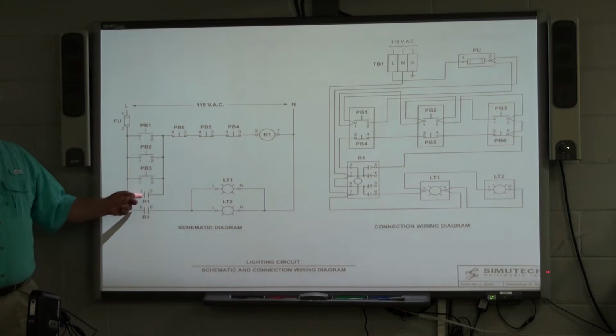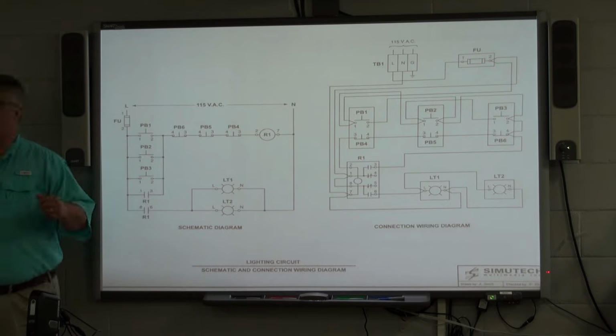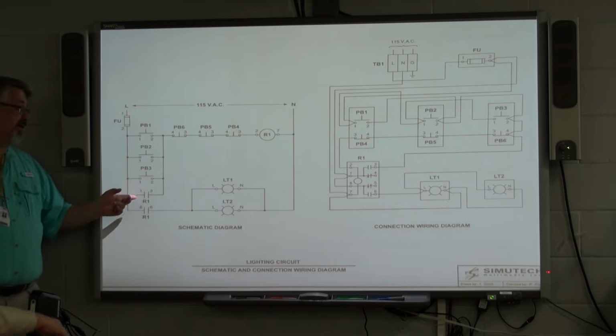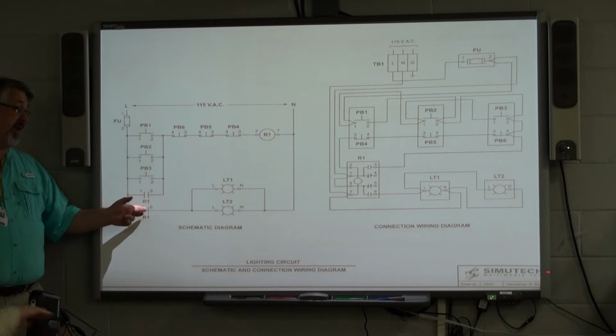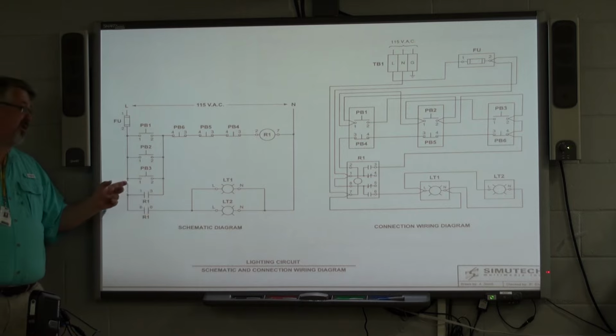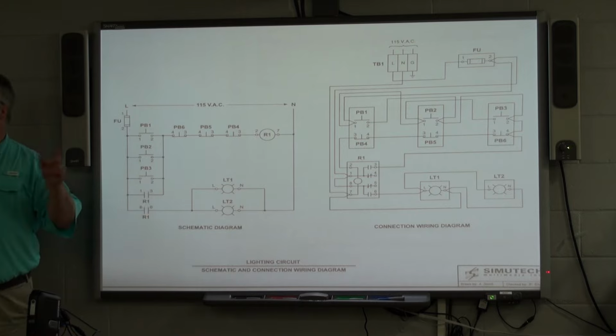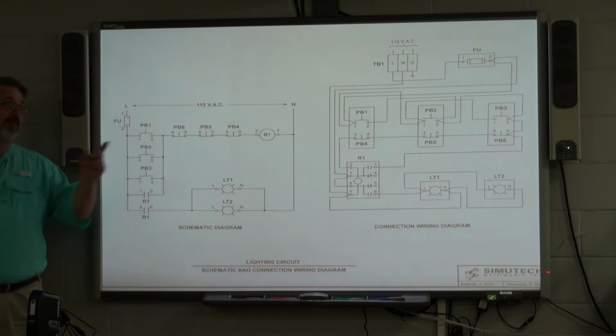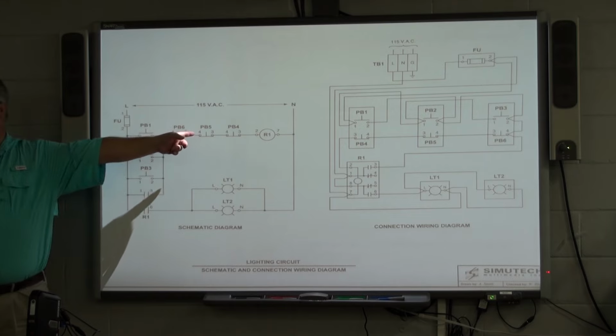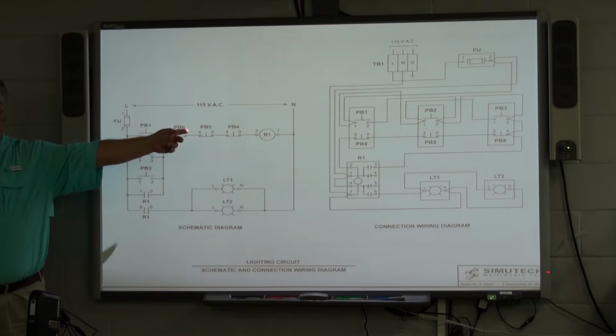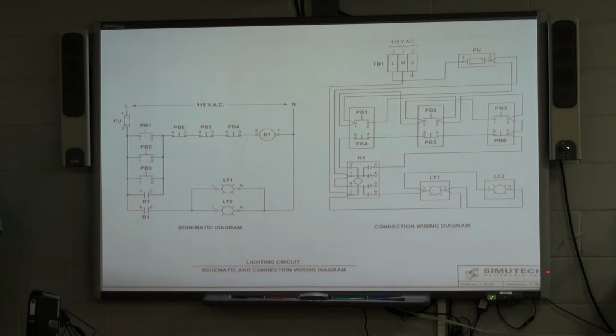Now if it weren't for this part, these contacts, as soon as we let go of that button, that light would go off because the coil would no longer be energized and we'd have no voltage. But what we're doing is through pins 1 and 3, just like we have through 8 and 6 to light the bulbs, we're providing a voltage through them that's in parallel with all the switches that keeps that voltage active to that coil. And that's what we call a latch.